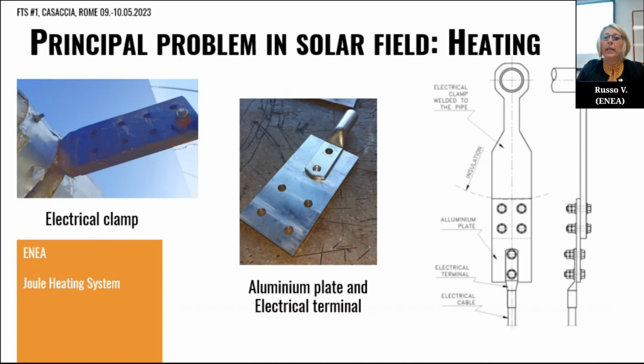Here are shown the electrical clamps connected to the receiver tube line in this picture. At this clamp are connected the cables coming from the generator. In this scheme, instead, there is represented the connection between the aluminum plate, shown in this picture, and the electric cable. It is very important to ensure an excellent contact between the end of the terminal of the electric cable and the aluminum plate, in order to avoid electrical dispersion.